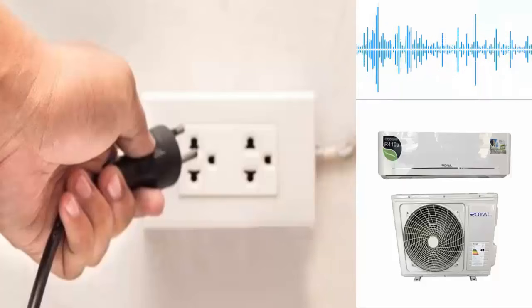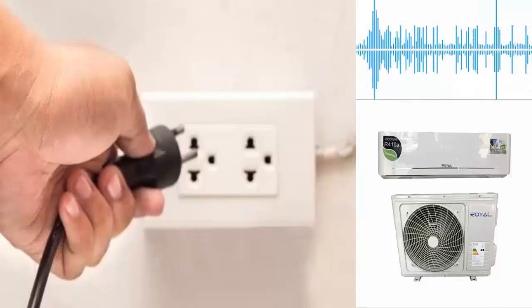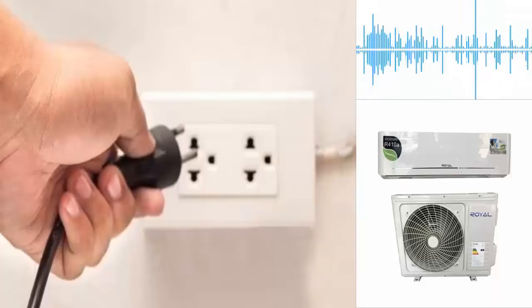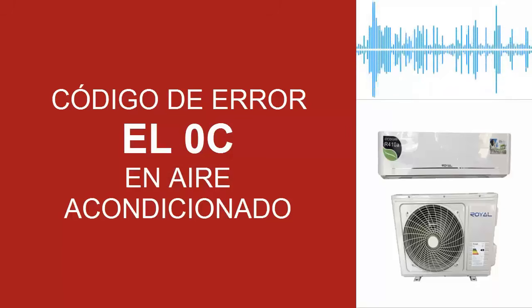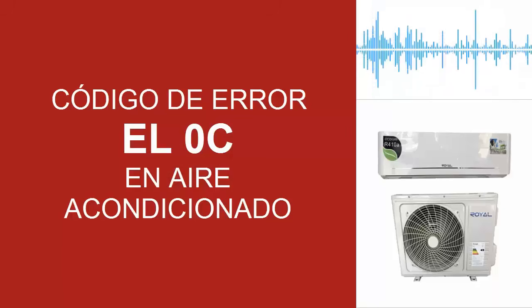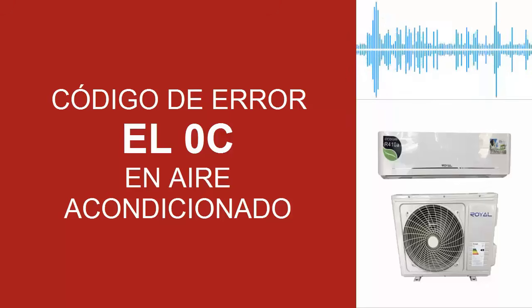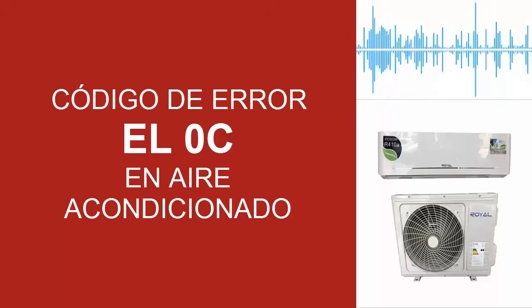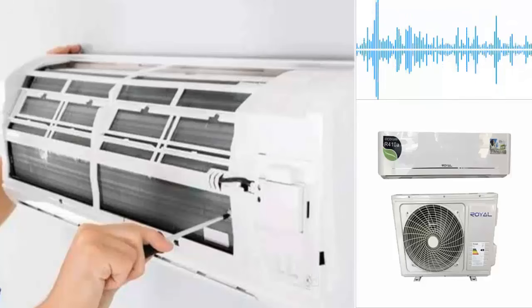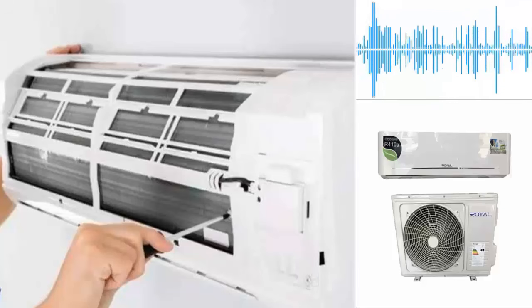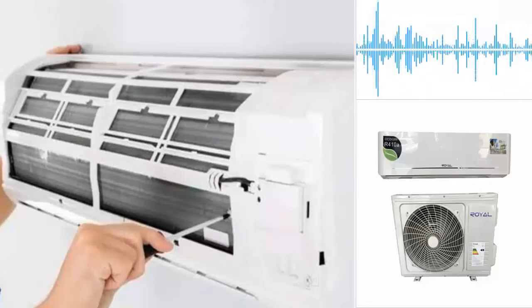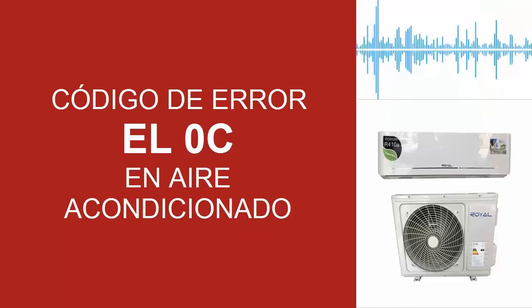To temporarily clear the error code, you can try disconnecting it from the electricity for several minutes, and attempt to turn it on directly if possible. If the equipment has normal electricity consumption, then perform the following checks. A. Clean air filters in the indoor unit, as clogged filters can cause high readings in room temperature, leading to faults incorrectly related to gas shortage.